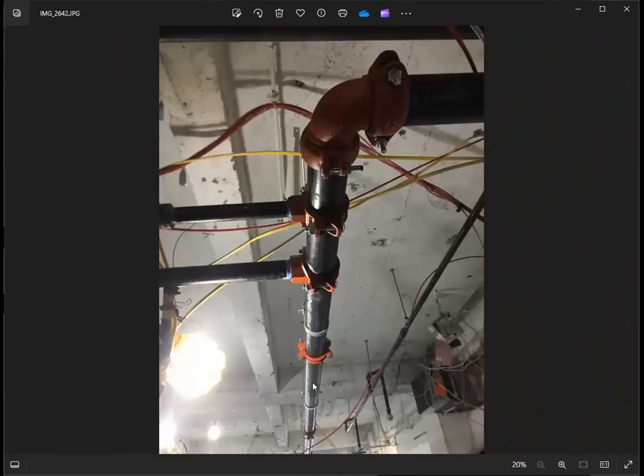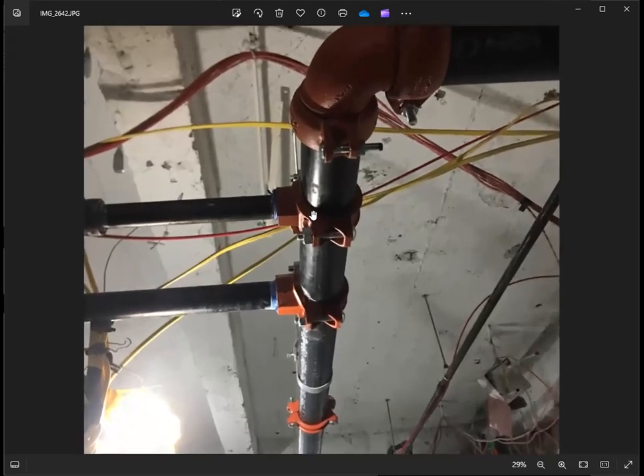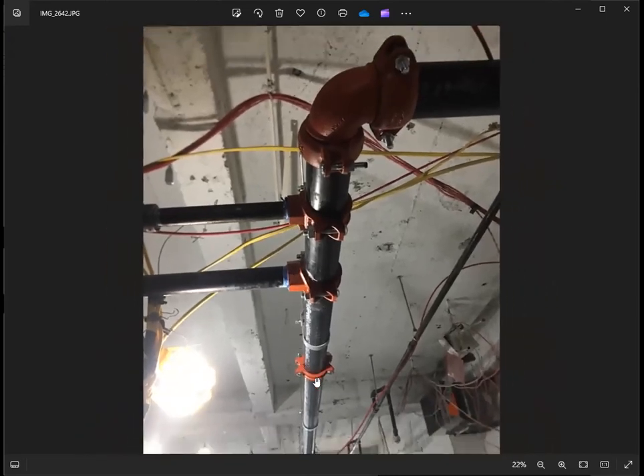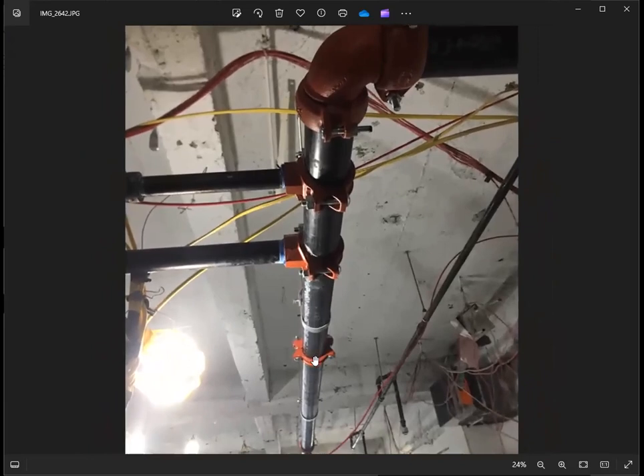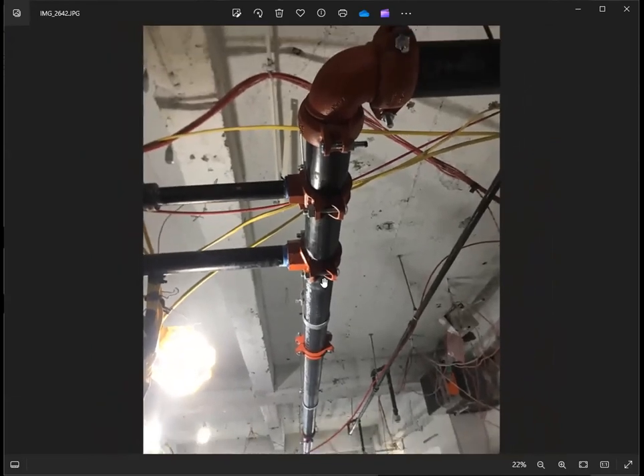And yeah, for the hydro test, all those joints, couplings, elbows should be visibly inspected. No droplets, no trace of water dropping. So there are some instances or some conditions where some pressure still holds, but some leaks are found in joints and connections. So you need to address that during the test and tell the contractor.